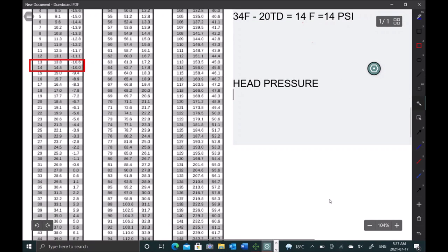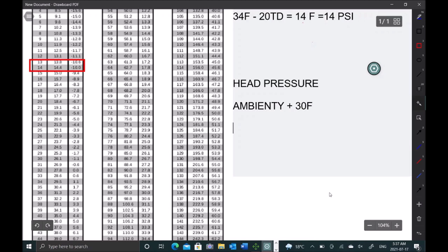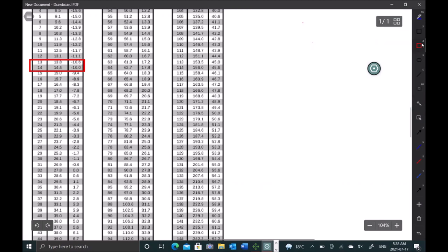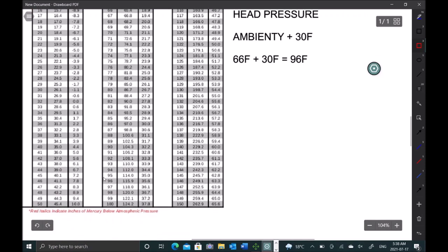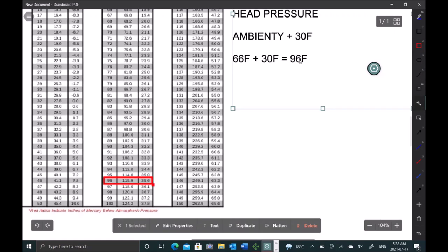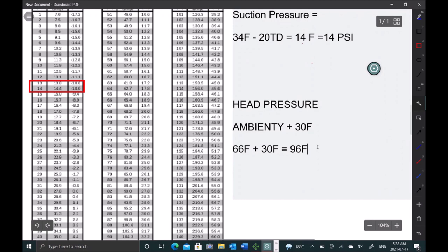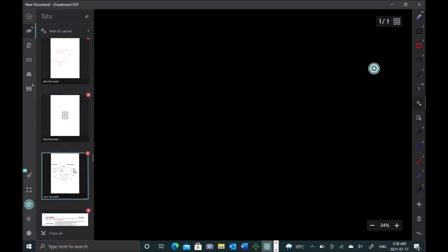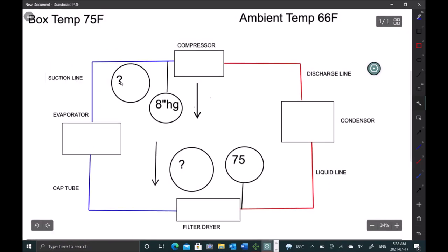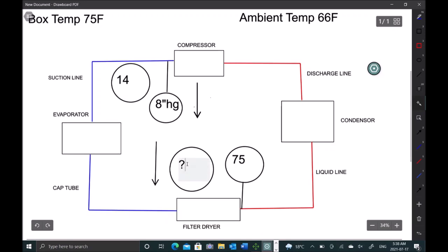All right, and for our head pressure we're going to go ambient plus 30 Fahrenheit. So we had 66 ambient, let's add 30 to that, gives us 96 Fahrenheit saturation. So let's go to our PT and see what we got for 96 Fahrenheit. And at 96 we're going to get 115. So we're looking for 14 PSI and 115 PSI. So let's go plug these into our diagram here. So 14 and 115.